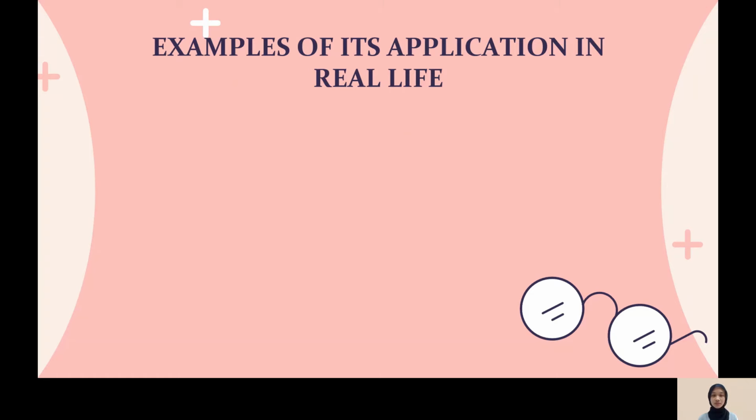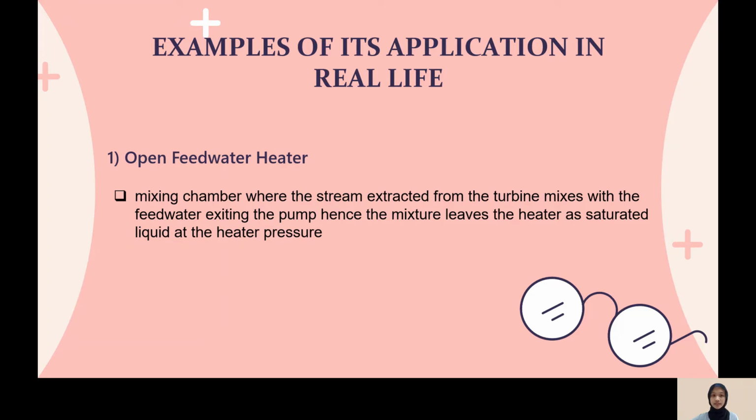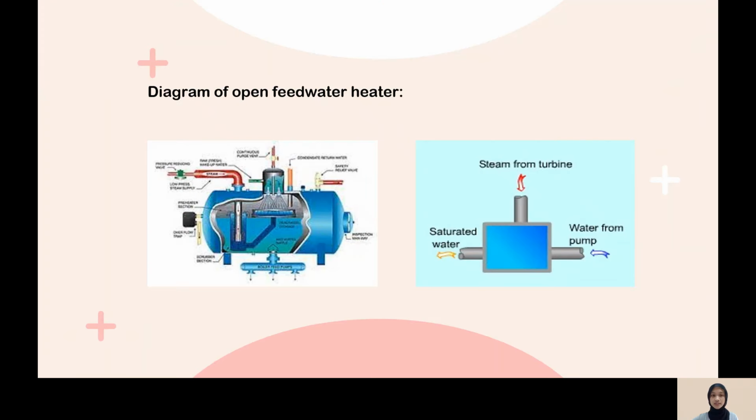Next is the examples of its application in real life. The first one is the open feed water heater. Open feed water heater is actually a mixing chamber where the stream extracted from the turbine mixes with the feed water exiting the pump. Hence, the mixture leaves the heater as saturated liquid at the heater pressure. So this is an example of diagram of open feed water heater.